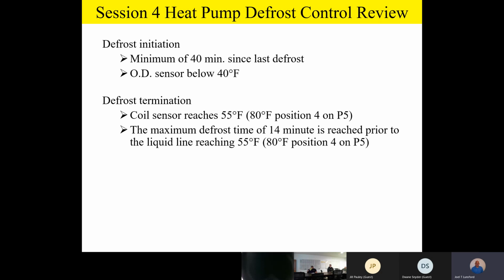In addition, defrost termination is going to take place when the coil sensor reaches 55 degrees. And by the way, there is another position on what we call the P5 jumper. On position 4, it'll take it up to an 80 degree termination. But normal defrost termination occurs when the coil temperature sensor reaches 55 degrees Fahrenheit. Plus, in case you have a bad coil sensor, there's a maximum defrost time, or time backup, of 14 minutes if that is reached prior to the liquid line reaching that 55 degree termination point. Any questions or comments on that so far?